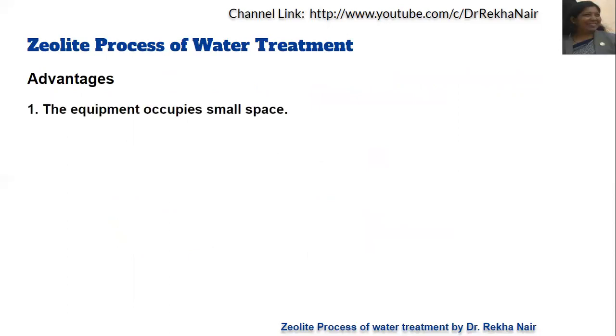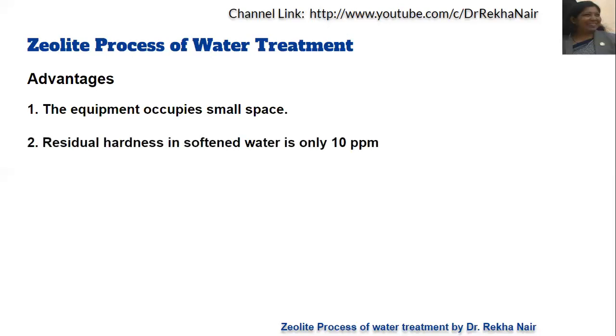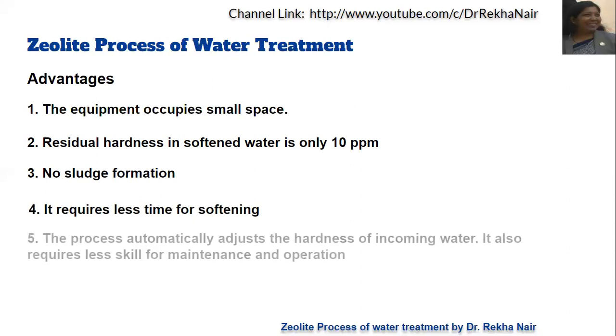The advantages of the zeolite process are: the equipment occupies small space, unlike lime-soda where the equipment was larger; the residual hardness of softened water is only 10 ppm, which was more in the case of lime-soda; there is no sludge formation, whereas lime-soda produced a lot of sludge that was difficult to manage; it requires less time for the softening process; the process automatically adjusts to the hardness of incoming water; and it requires less skill for maintenance and operation.